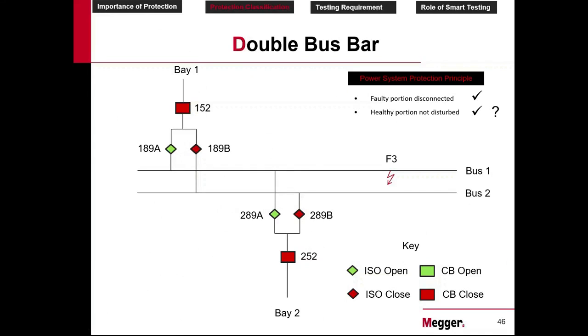So let's assume it's 30 seconds for one isolator to operate. That means for two isolators, it's 1 minute. So for one bay, you take 1 minute. So in a 40 bay substation, if you are operating all the isolators, you are going to take 40 minutes to do this. So roughly 40 minutes supply interruption.